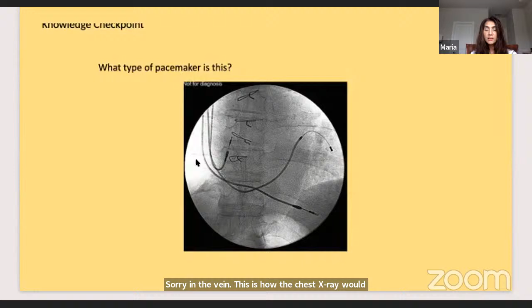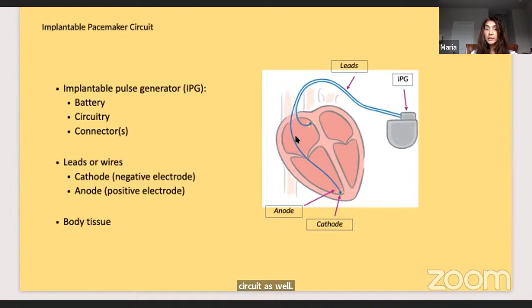What are the components of the pacemaker system? The pacemaker will have a battery, circuitry, and connectors to connect the leads to the pacemaker system. The leads are wires which go into the heart. Since these are insulated electrical wires, there's a cathode and an anode present. These are traditionally bipolar leads these days. Body tissue is part of the circuit in the sense that it transmits the electrical impulses cell to cell at the electrode-tissue interface. When the lead impedance is measured, it includes this portion of the circuit as well. So you have the pulse generator, the leads, and the body tissue, and this completes the circuit.